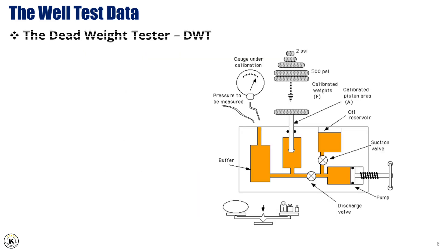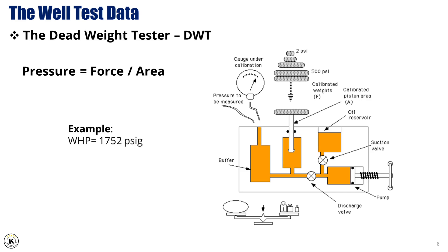The deadweight tester (DWT) is a highly accurate device used to calibrate pressure gauges and pressure transducers. It works on the principle that pressure equals force divided by area. Force is applied using a known weight (deadweight) that presses down on a piston or plunger, and the area refers to the cross-sectional area of that piston. By using precise, known weights, the DWT can provide highly accurate pressure measurements.